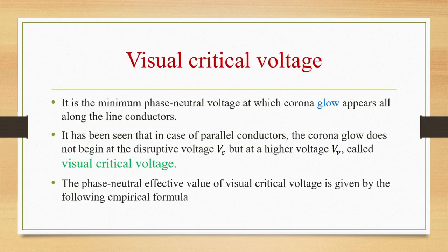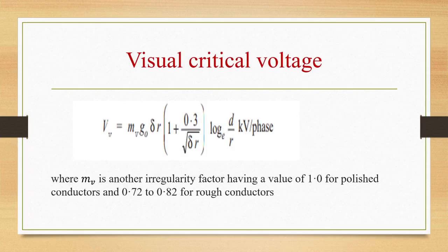Now we will see the visual critical voltage. Visual critical voltage is the minimum phase neutral voltage at which corona glow will appear all along the line conductors. So in case of parallel conductors, corona glow does not begin at the disruptive voltage Vc but at a higher voltage Vv, which is called the visual critical voltage. The phase neutral effective value of visual critical voltage is given by the following empirical formula: Vv is equal to mv g naught delta R into 1 plus 0.3 by root delta R log d by R base e kilovolt per phase, where mv is another irregularity factor having a value of 1 for polished conductors and 0.72 to 0.82 for rough conductors.